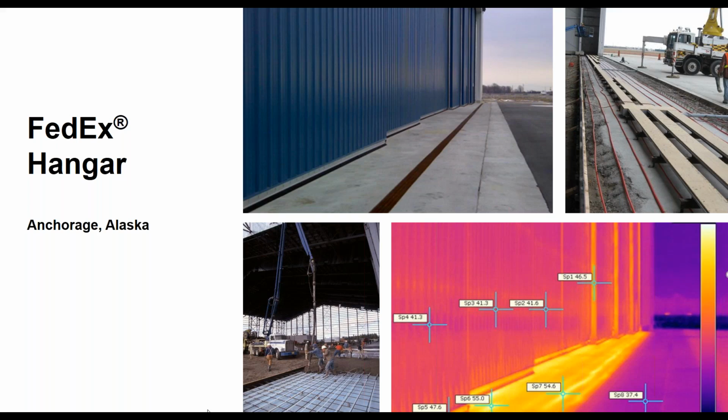So some of the unique challenges from an installation standpoint and the design standpoint, like I talked about, is, one, these hangars have very thick slabs. Like I said, 14-inch, 12-inch slab, not at all uncommon. So dealing with the design considerations there might mean we need to run a higher water temperature than you might expect if our pipe is 8 inches below the slab or 7 inches below the slab than if we were up at 2 inches below.